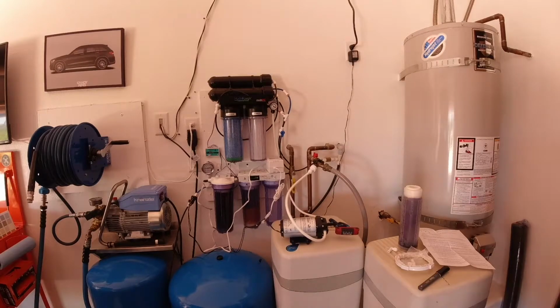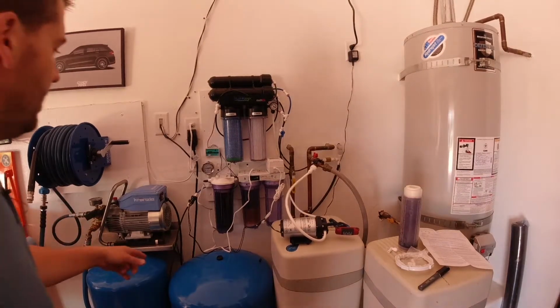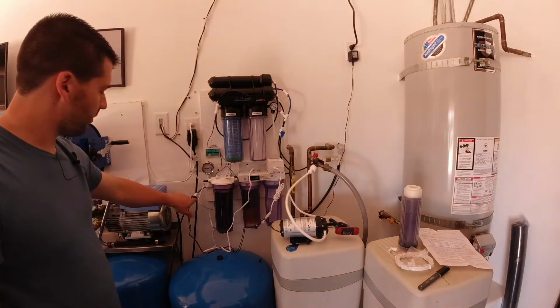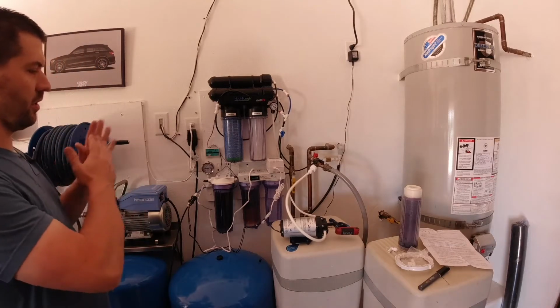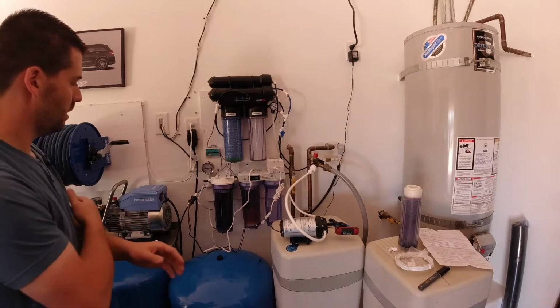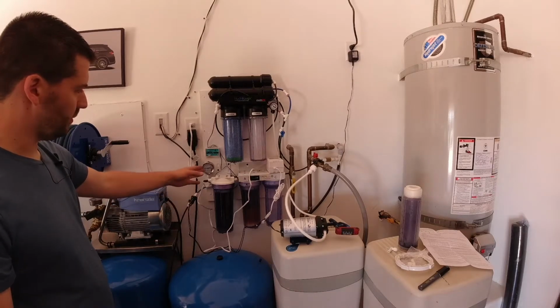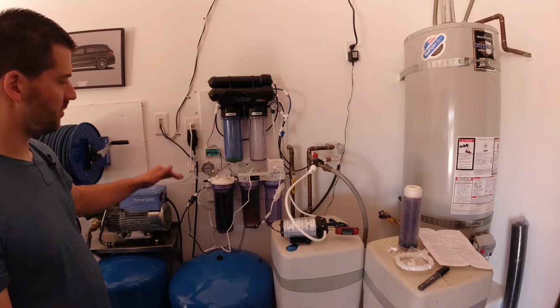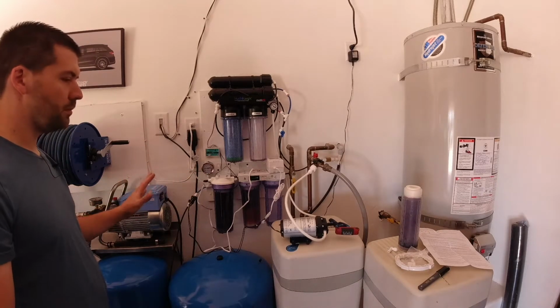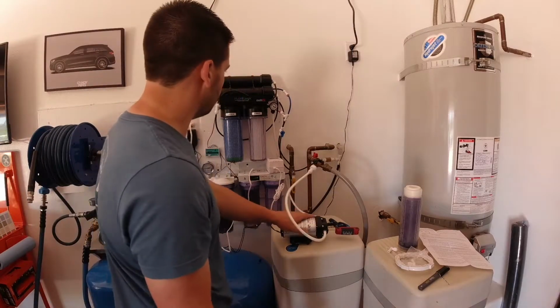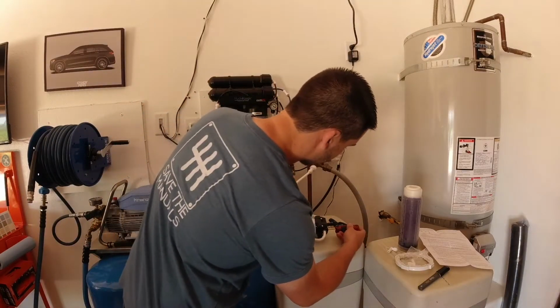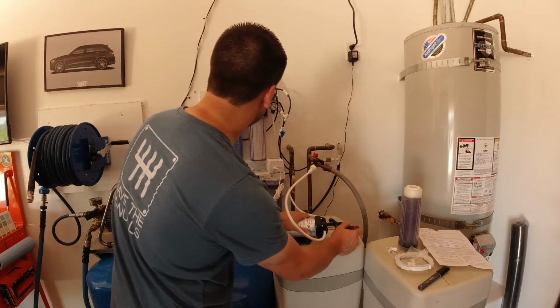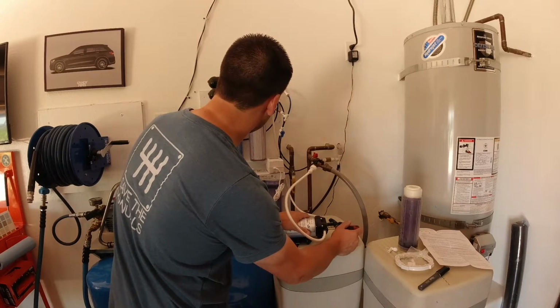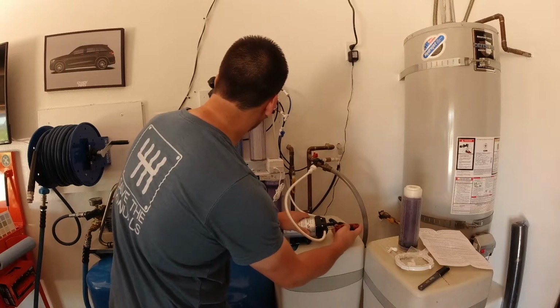Alright, so on the pressure switch output side, tightening this screw increases the pressure, both the turn-on and turn-off points. When turned in all the way, it seems to turn on at 40 and turn off at 60, which might be a little too high. Turning this in increases the operating pressure, so I'm at like 56 right now, 60.